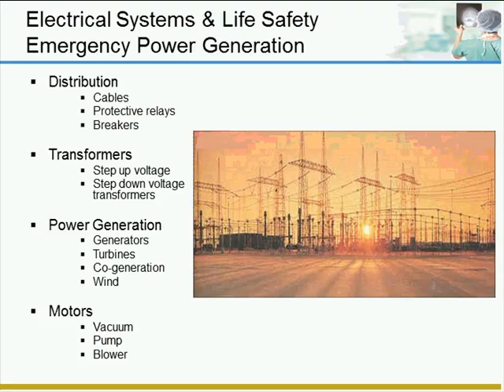Main transformers will be liquid-filled, oil-cooled units, which are typically outside. Some of the other units will be dry-type units, air-cooled, which will be found typically inside. And then you have the bucket-type pole-mounted units.